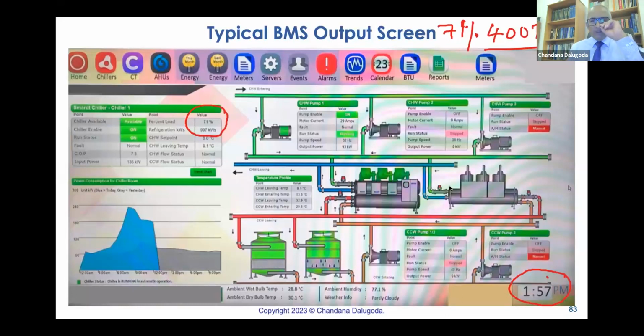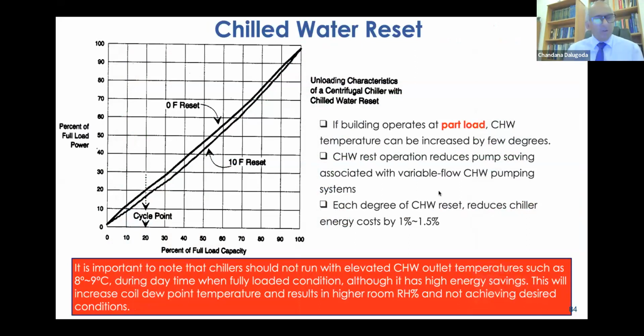A lot of strategies have been put into operation. I'll give you some of these, not all that is implemented at Ceylon Towers, but say the first one is chilled water reset. Chilled water reset is heavily misused in Sri Lanka, heavily misused, because chilled water reset gives energy reduction instantly. So what happens is, if this gets known by the GM of the hotel, he always does the chilled water reset by himself. Chiller outlet temperature is 7 degrees C, return 12. Chilled water reset is during part load operation, we raise the temperature 7 to 8, probably 8 to 9. But surely it is under part load, that is during night, a rainy day.